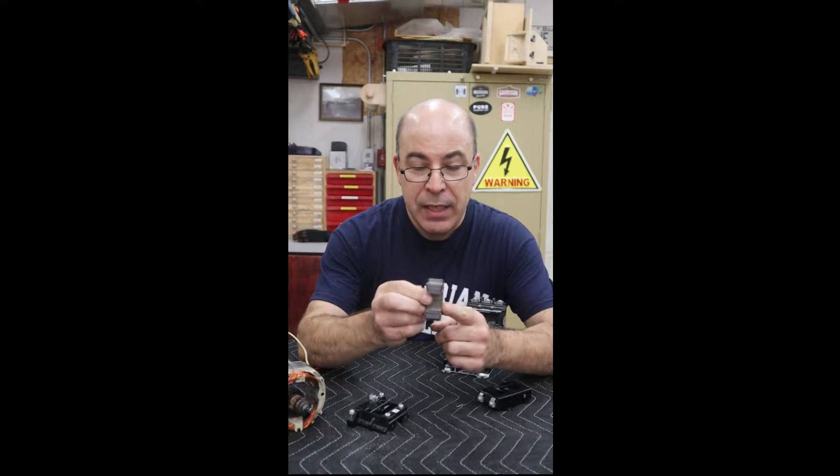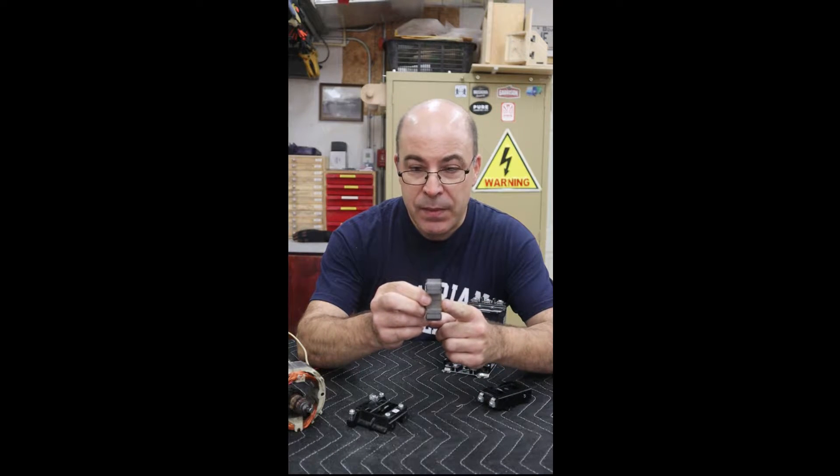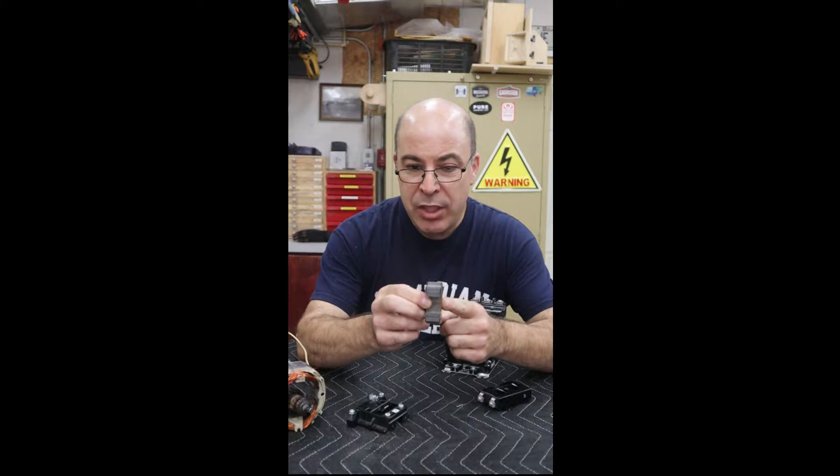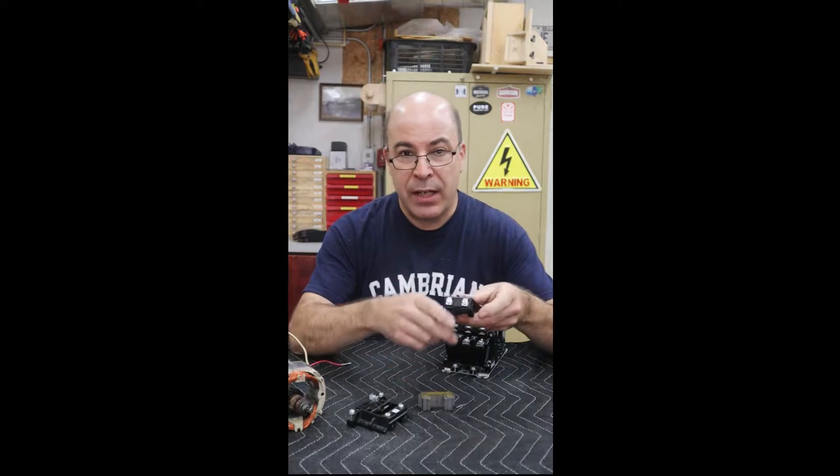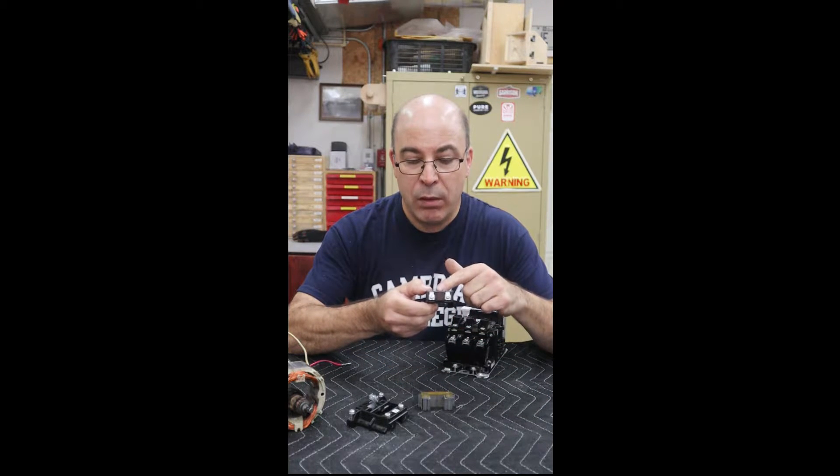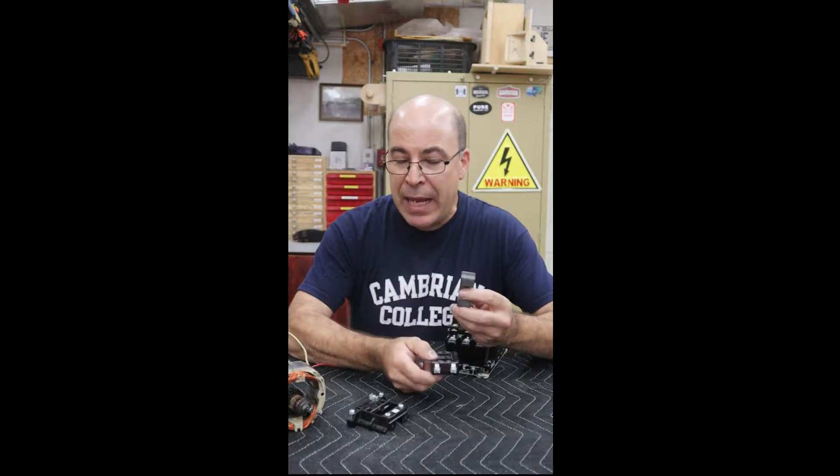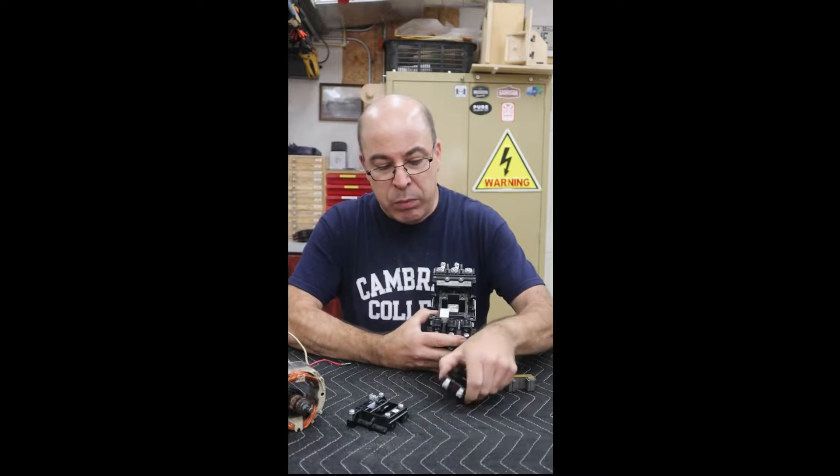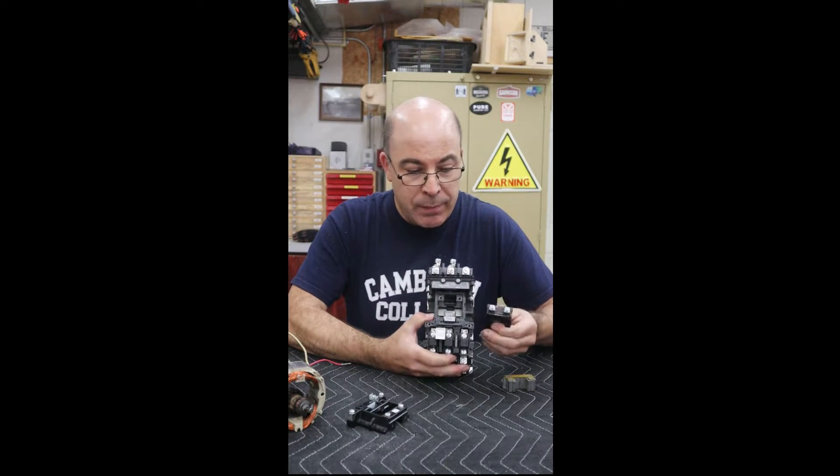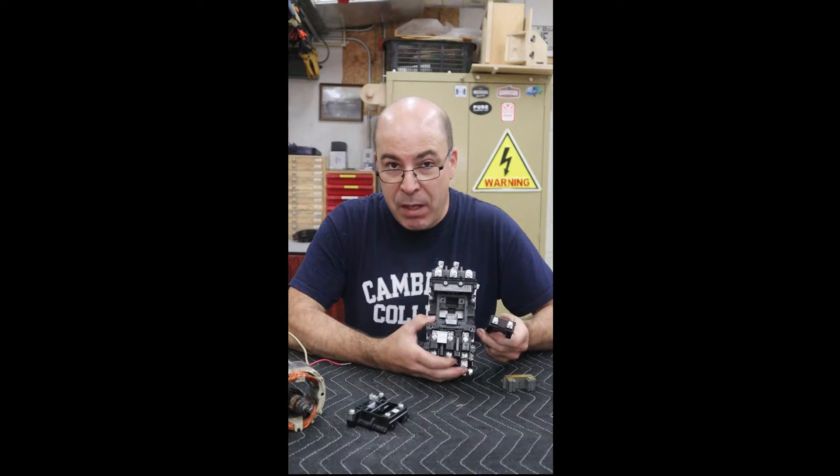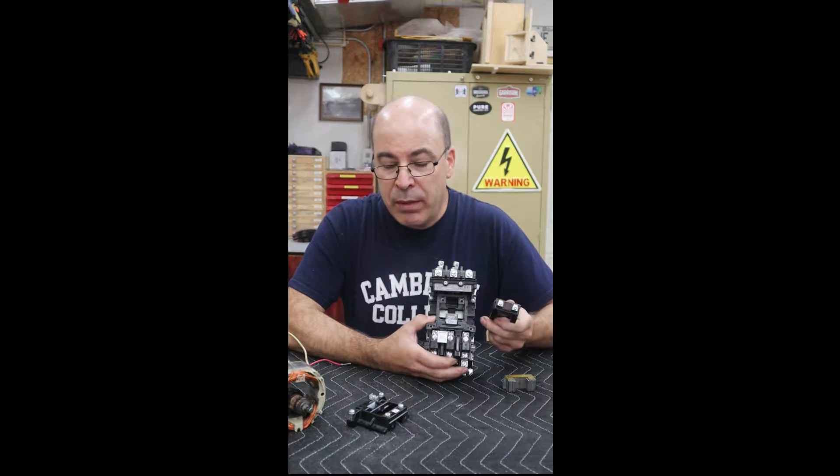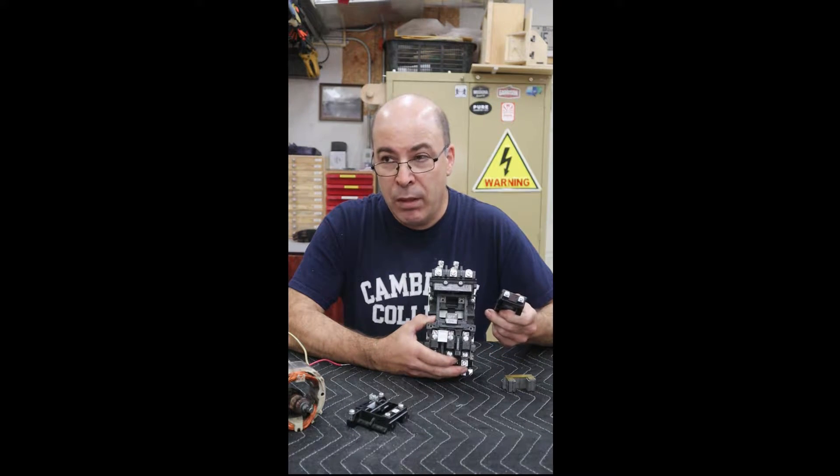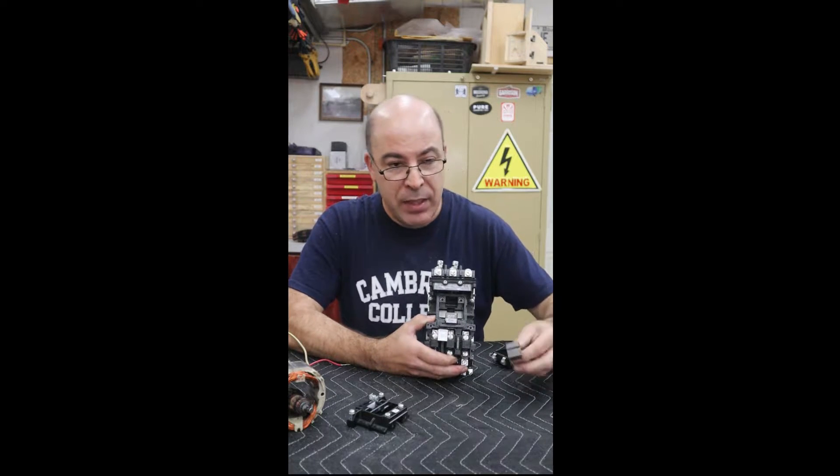The reason being is if we did not do this, when we had the machine running and we were actually running alternating current through this coil, this steel if it was solid would actually heat up and eventually the contactor would get so hot that the plastic would start to melt. This is one of the critical areas of why we have to use laminated steel.